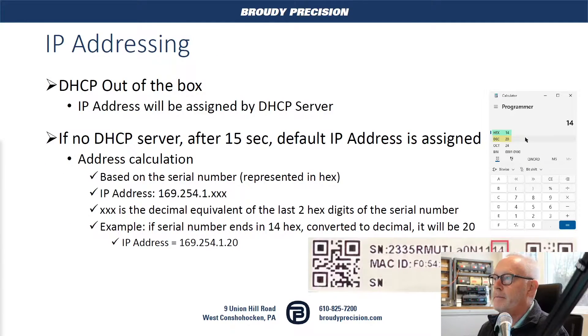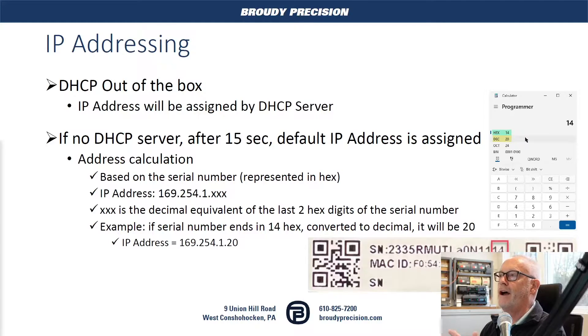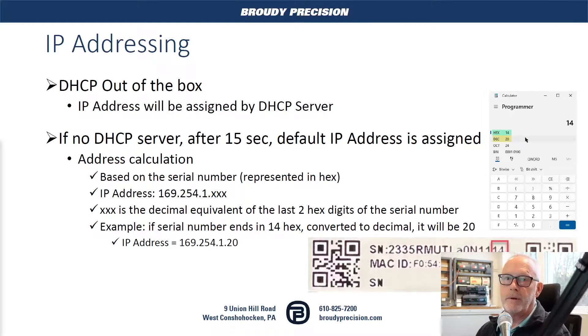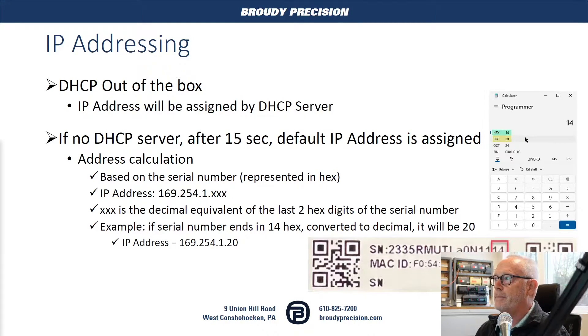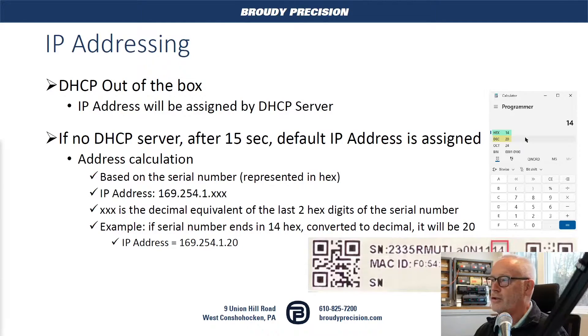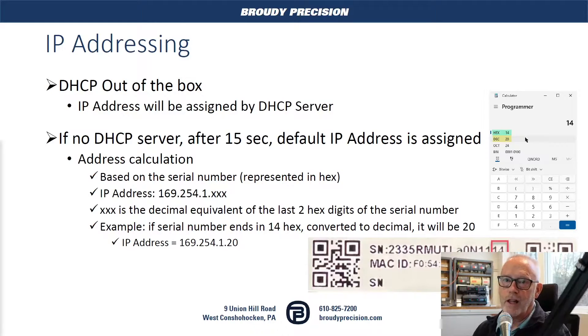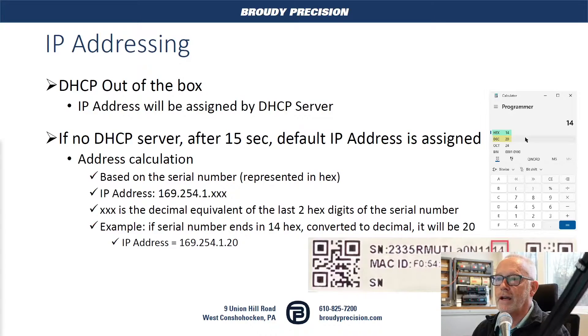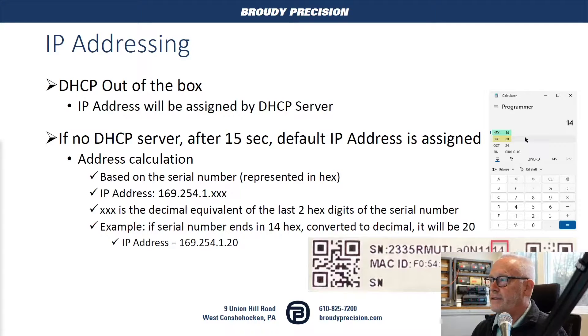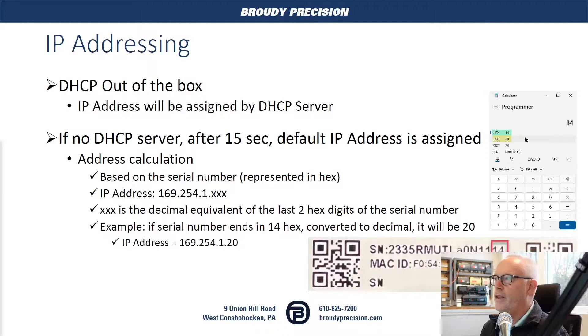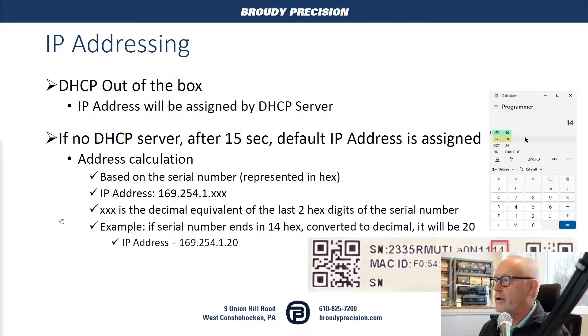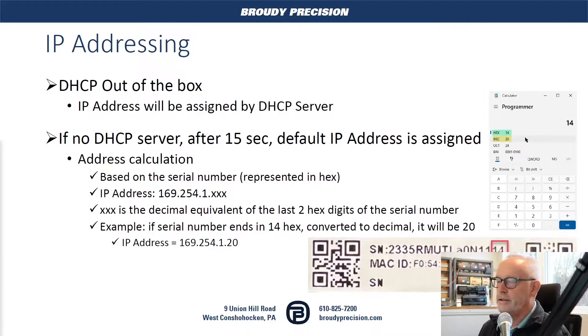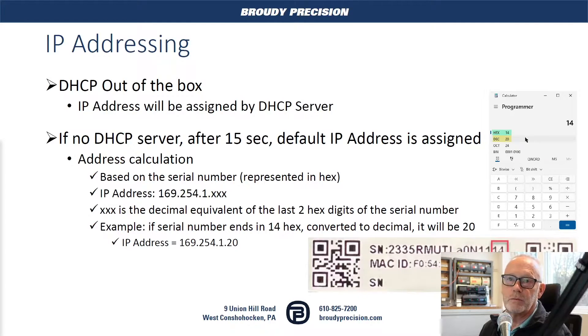Obviously, with BACnet IP controllers, you have IP addressing that you have to deal with on the controllers. Out of the box, the controllers are set up for DHCP. So whatever the DHCP server sets up for the IP address, that's what gets assigned to the controller. If there is no DHCP server available, after 15 seconds, it's going to go to a default address. And that default address is going to be 169.254.1.aNumber. And the way that works is if you look at the serial number, and I have an example on here of one of my unitary controllers, the last two digits is 14. This serial number is actually a hexadecimal number.